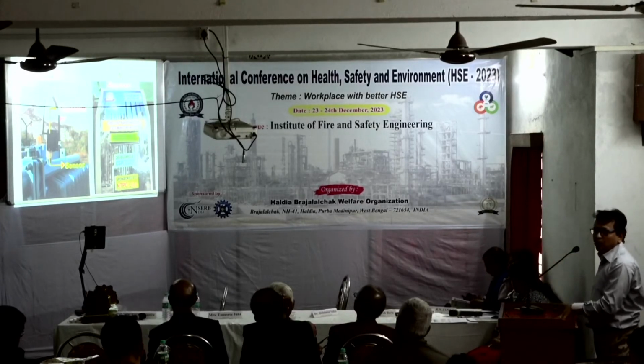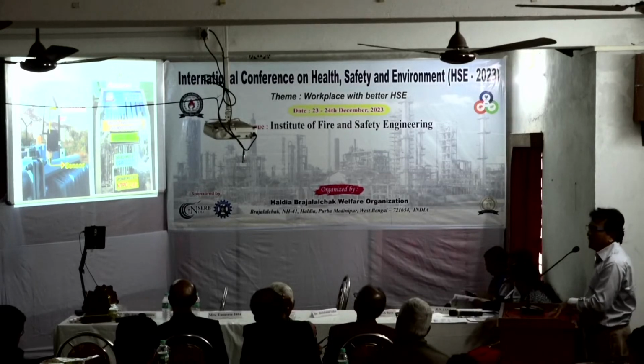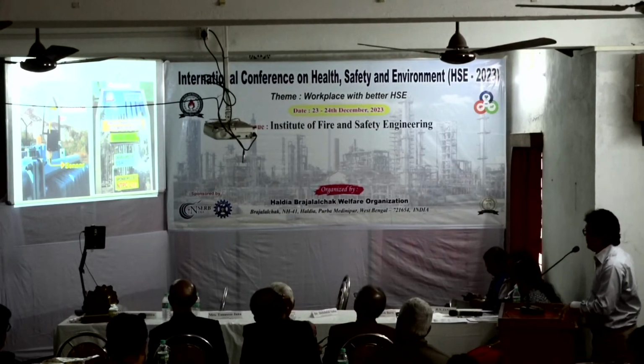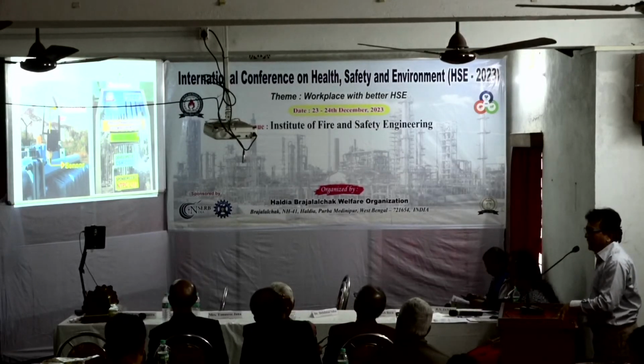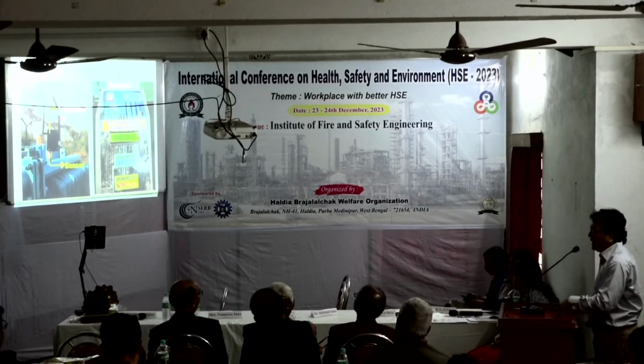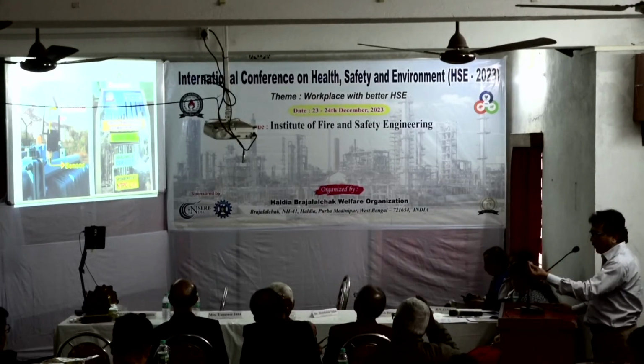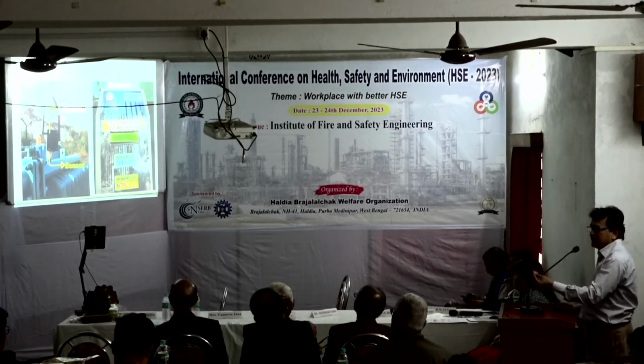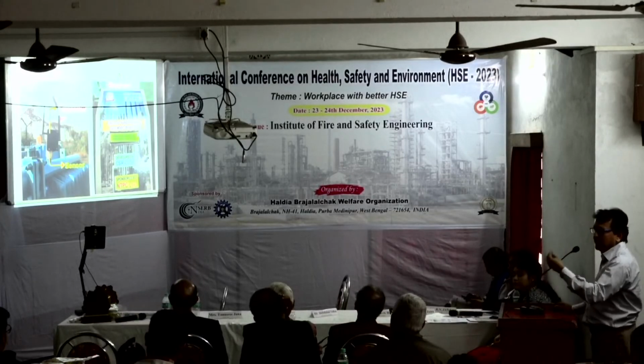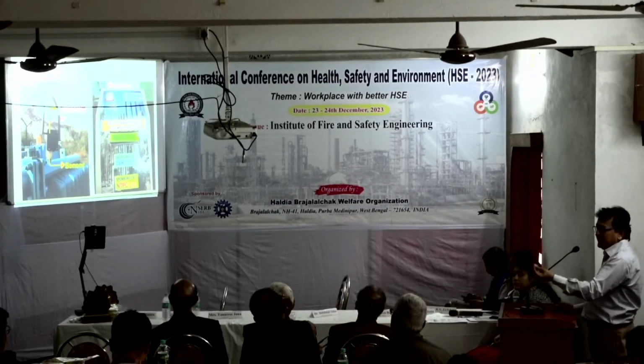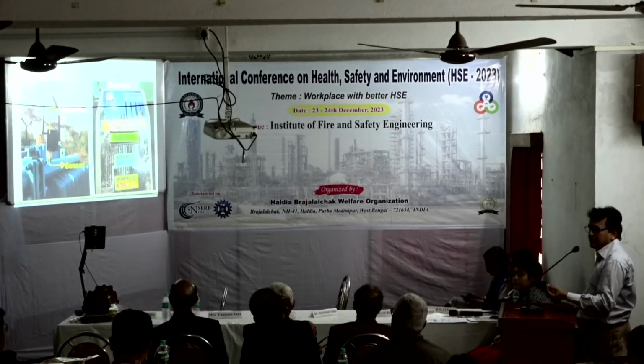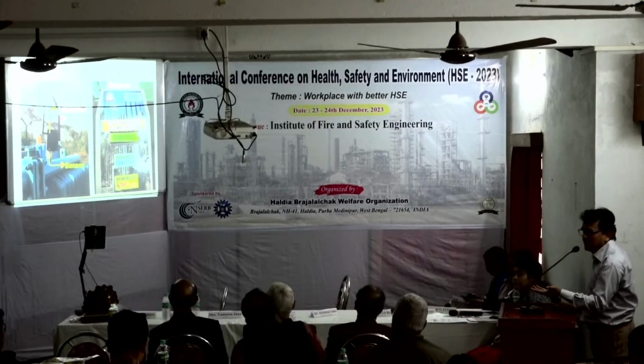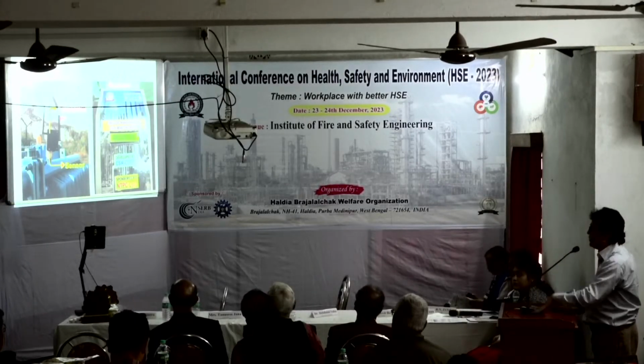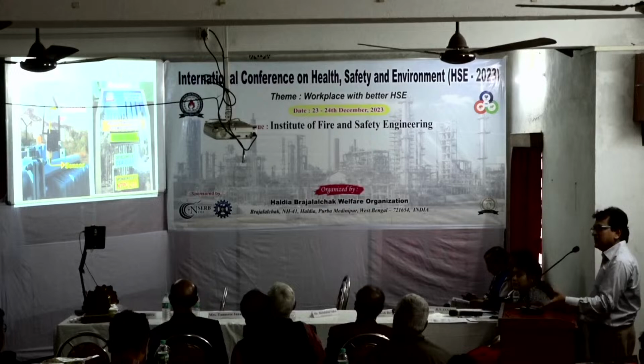So what is the current detection technique? The current detection technique is an offline process called the Karl-Fischer technique. If you take a water-oil aliquot and send it to the lab, the Karl-Fischer process there detects and measures the moisture content. If the moisture content is more than the limit, they stop the transformer and change the oil.